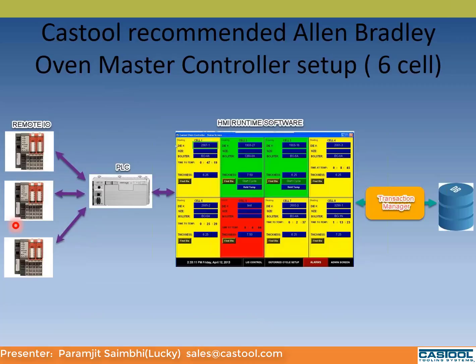So here I'm showing you the remote I/Os on the left hand side. They would be per cell, and then you have a centralized PLC located in the master controller, and you have the HMI runtime software running, showing you multiple cells running. And then you have the transaction manager, which is optional. So what it is, you would save the data coming from the PLCs, from the remote I/Os, let's say the temperatures, when the cycle was started, when it stopped, when it was unloaded, to a database.